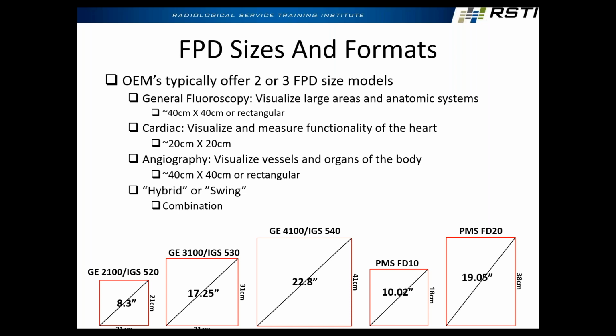So if you have GE systems, they're gonna be the GE 2100, Innova 2100 or the IGS 520. The 21 is the size of the detector, 21 cm by 21 cm. Their 4100 is an angio. So that's 41 centimeters, or the IGS 540. So angio means vessels. So if I want to look at a clog in a leg artery, it's running down the leg. If I only had the small detector, I can do angio studies with cardiac, but I have a lot more images. The detector is smaller.